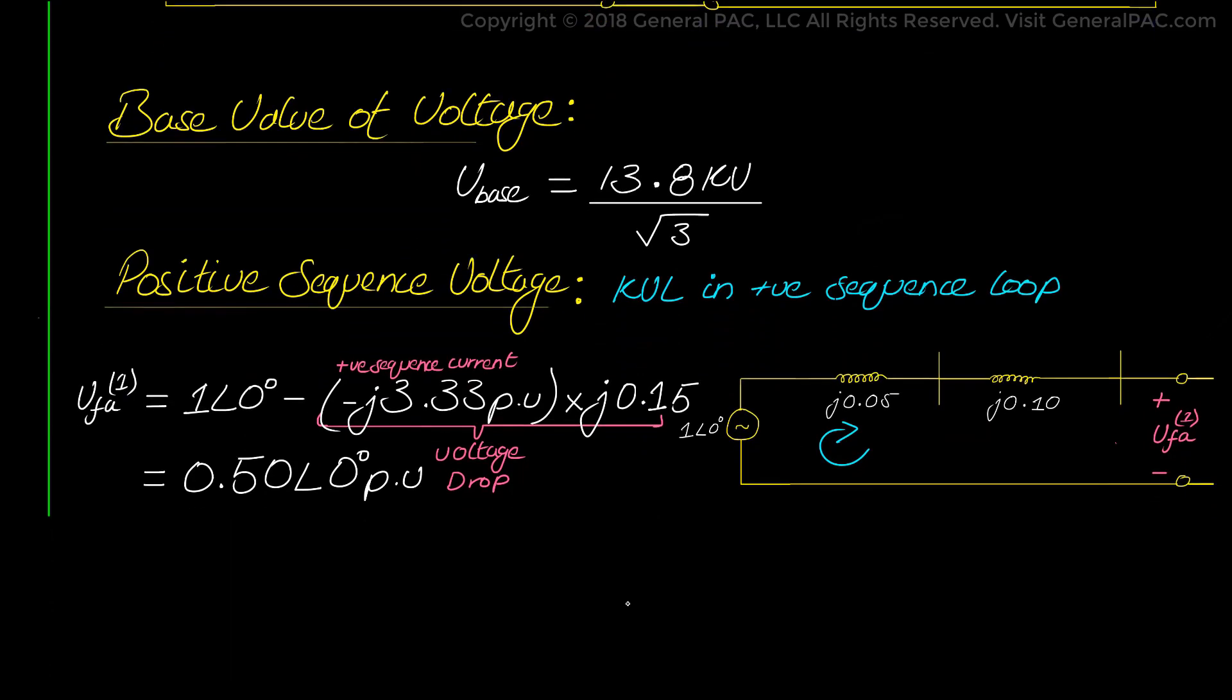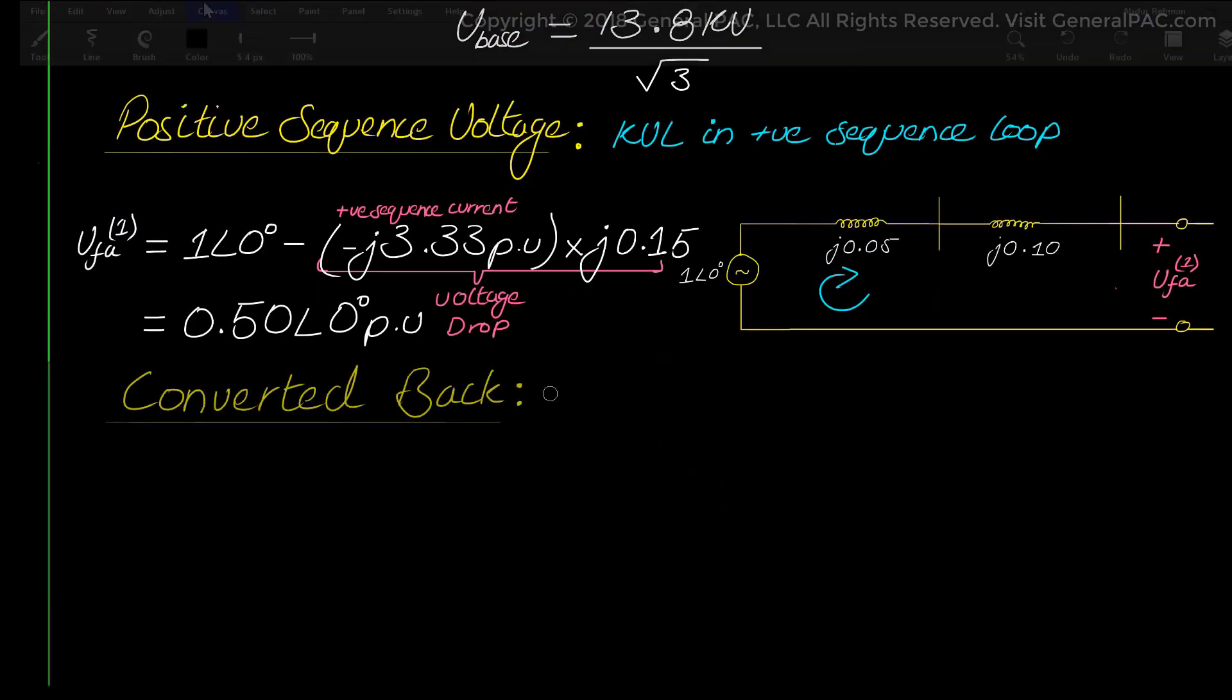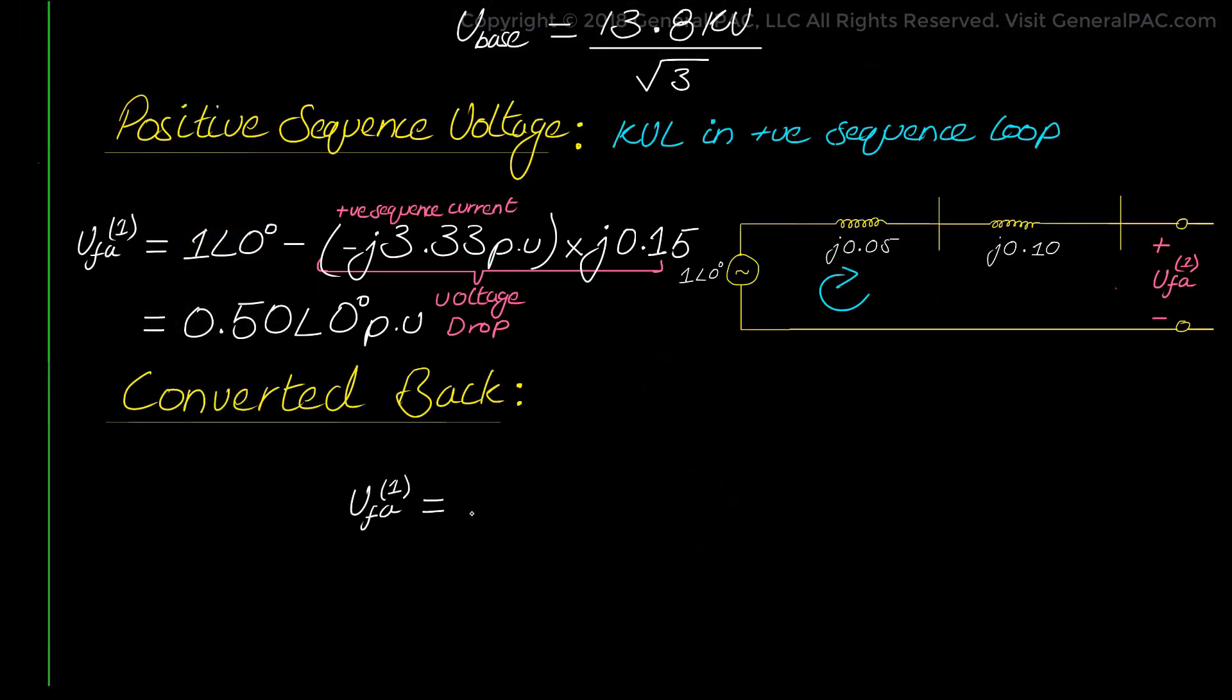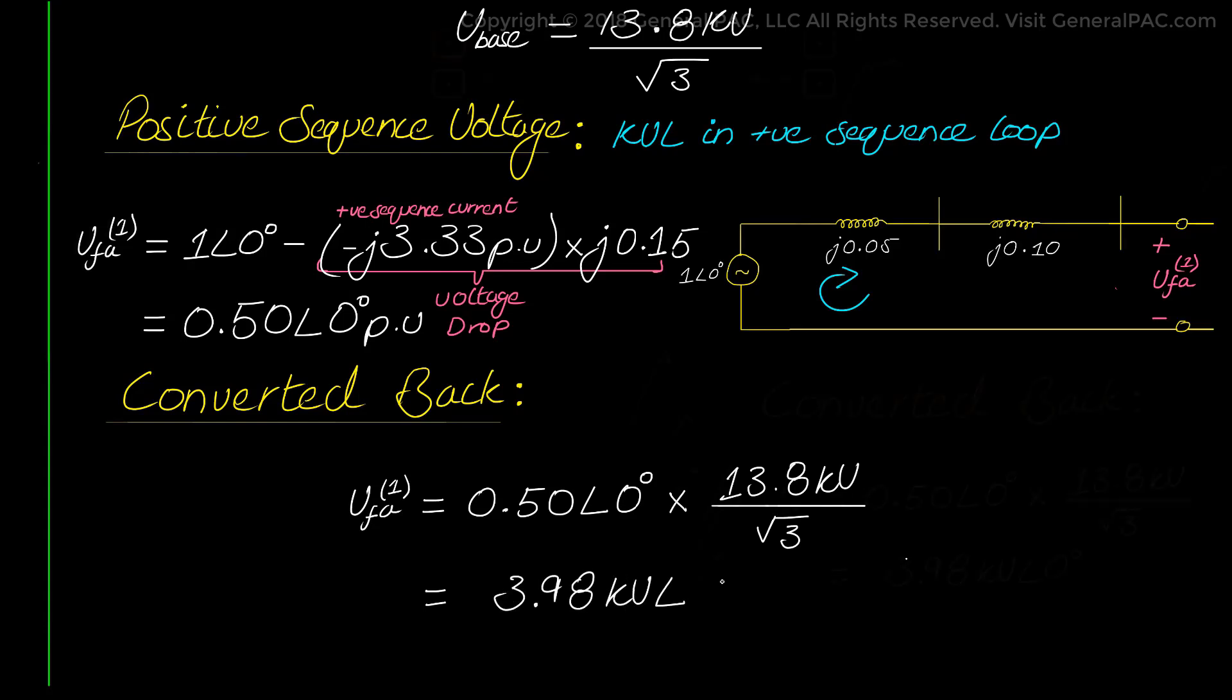Now this is a per unit value, and we need to convert this value to sequence voltage quantities. And we do this by simply multiplying the base value that we calculated earlier, which gives us the positive sequence voltage of 3.98 kV at the angle of 0 degrees.